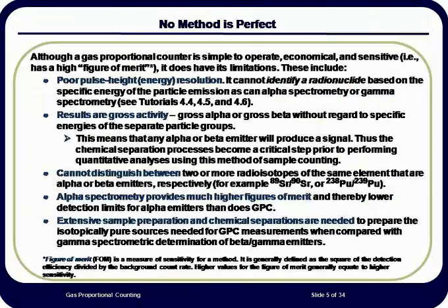It is very important to recognize that if radionuclide specific analysis is to be performed, chemical separations must be performed and must provide excellent separation from other radionuclides. This is because the gas proportional counter cannot discriminate between alpha particles of different energy or beta particles of different energy. It can, however, differentiate between alpha and beta particles. The resulting gas proportional counter output is total counts for alpha or beta.